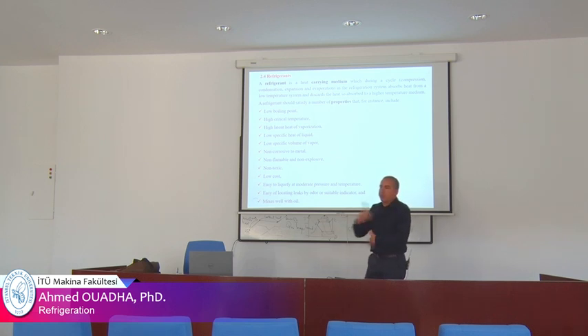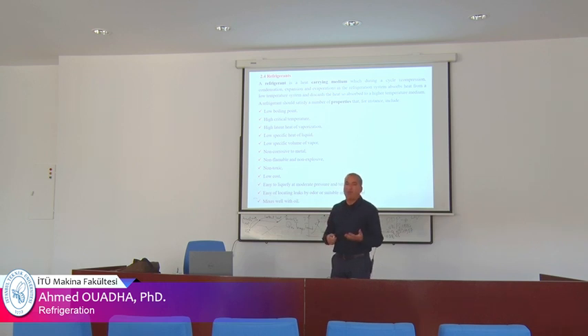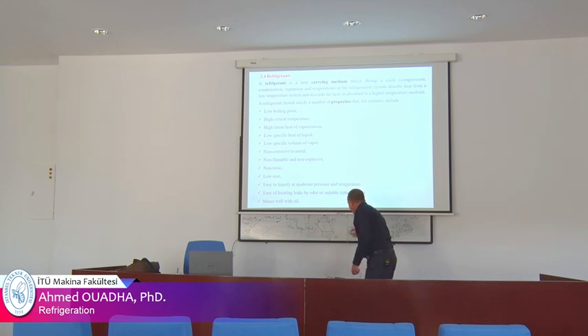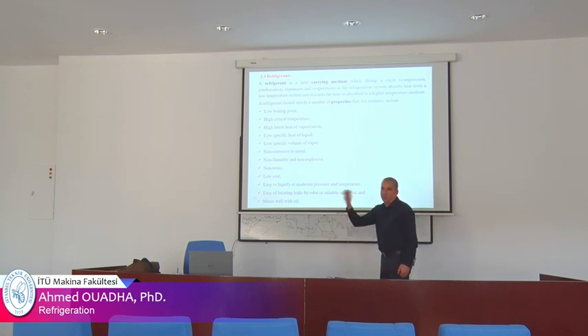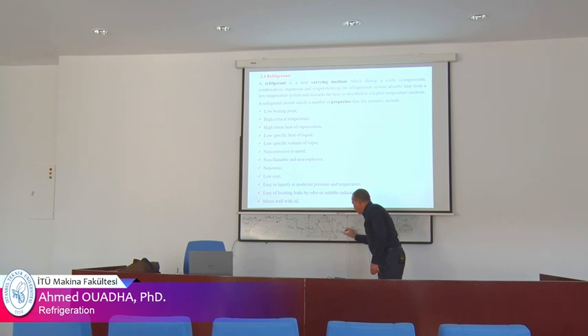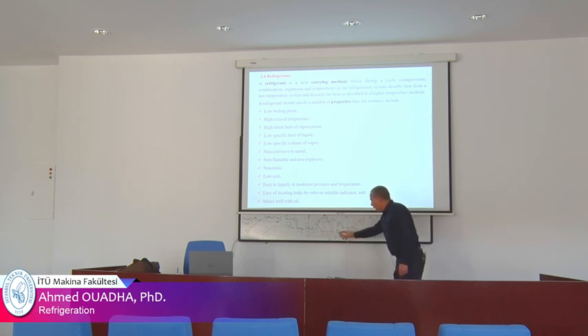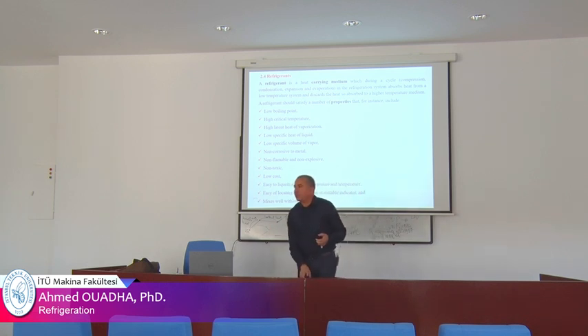And the industry has developed another type of refrigerant. This type of refrigerant is HFC. They replace the chlorine by hydrogen. From the example of CFC, for example, R12, which has been used in domestic refrigerators. The example of HFC is R134a. So in the 90s, they used R134a for applications, for example, domestic refrigeration.